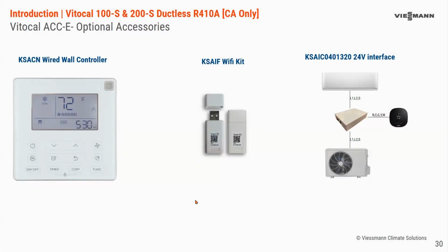And as far as accessories, a little bit more information on what we've been talking about. There are 3 main groups of accessories available. There's the wired wall controllers, the KSACN. There's a few different models depending on which indoor unit you're selecting. The wired controller allows full control of the indoor unit using the RS-485 protocol. So if there are additional functions, for example, in the high wall, having a turbo mode, that's when those nuances of having the correct control would matter. And some of them are programmable, some are not. So we have a suite of wired controllers available.